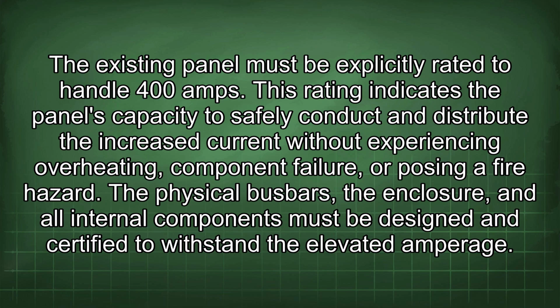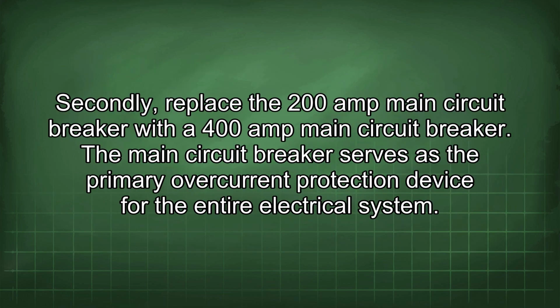This rating indicates the panel's capacity to safely conduct and distribute the increased current without experiencing overheating, component failure, or posing a fire hazard. The physical busbars, the enclosure, and all internal components must be designed and certified to withstand the elevated amperage. Secondly, replace the 200 amp main circuit breaker with a 400 amp main circuit breaker.